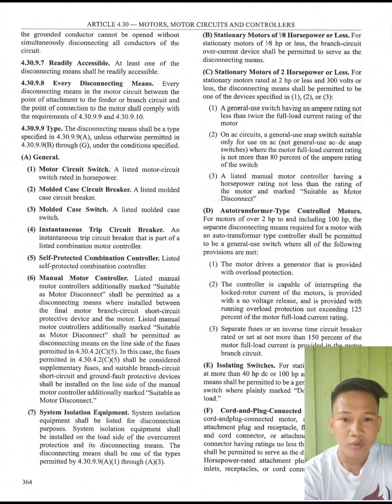7. System isolation equipment. System isolation equipment shall be listed for disconnection purposes. System isolation equipment shall be installed on the load side of the overcurrent protection and its disconnecting means. The disconnecting means shall be one of the types permitted by 430.109(A)(1) through (A)(3). Next is stationary motors of 1/8 horsepower or less. For stationary motors of 1/8 horsepower or less, the branch-circuit overcurrent device shall be permitted to serve as the disconnecting means.